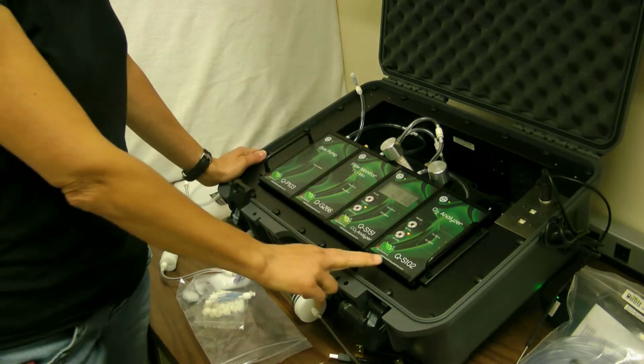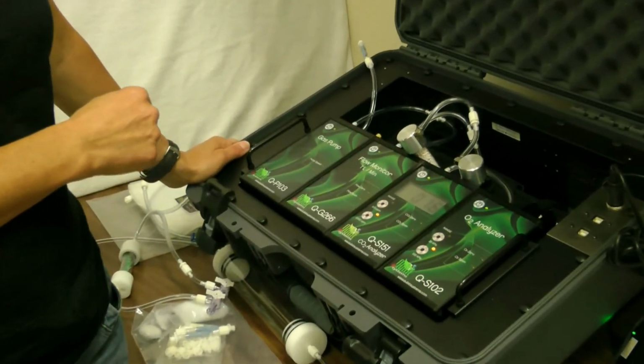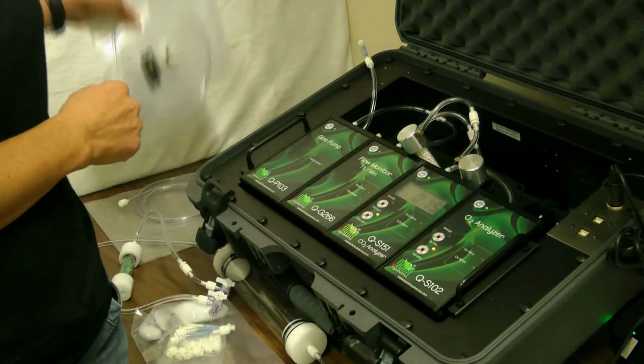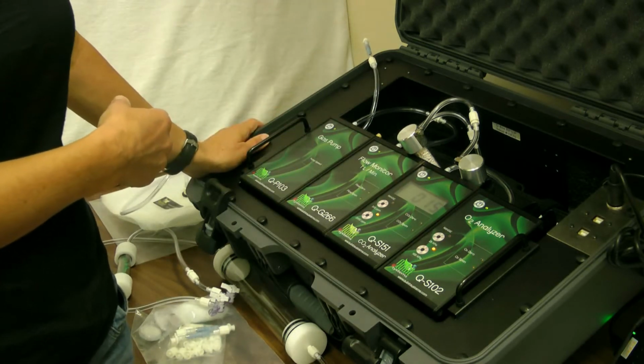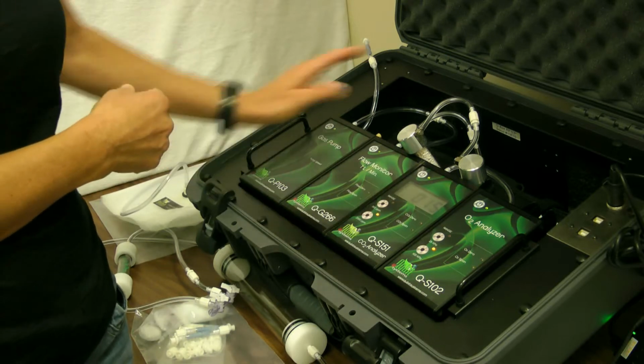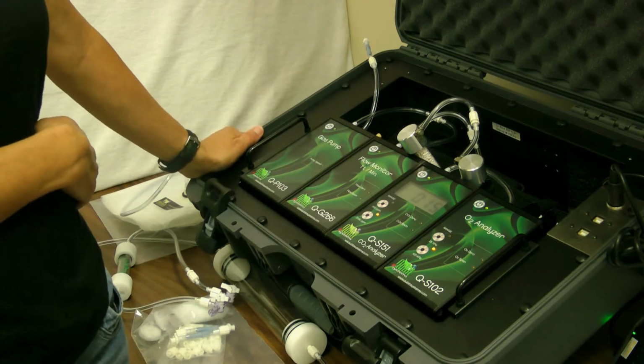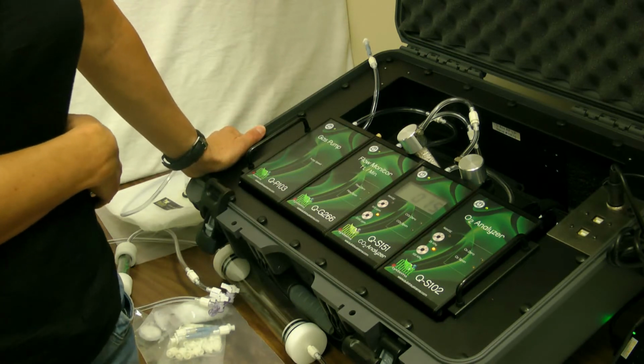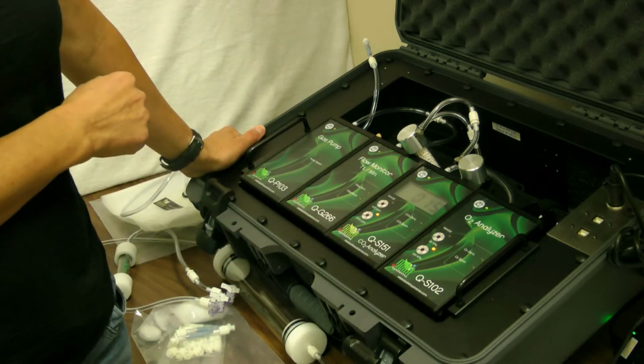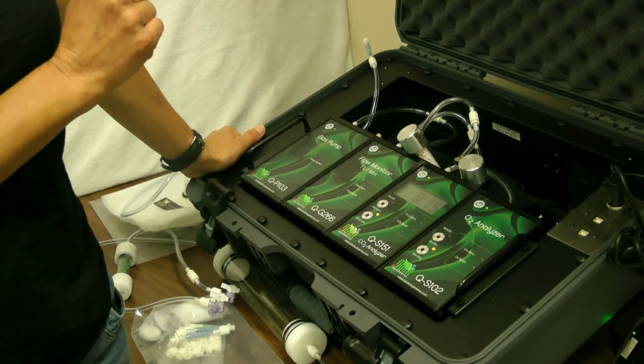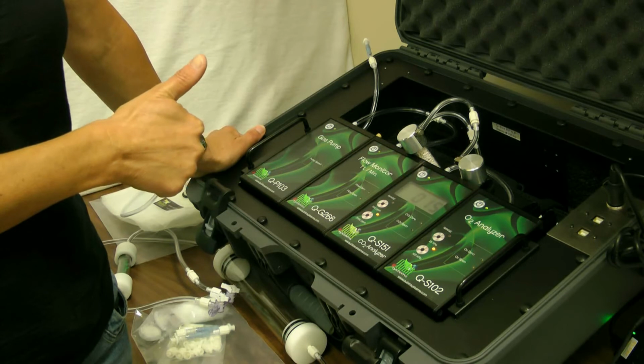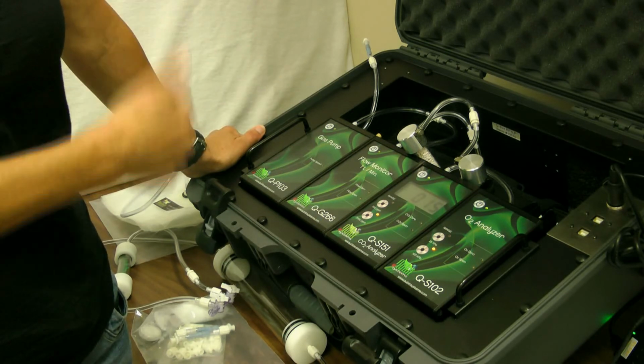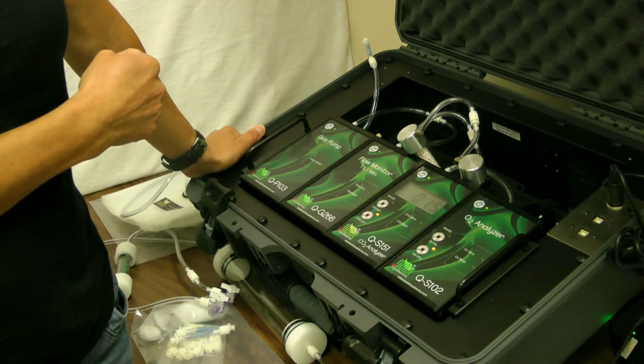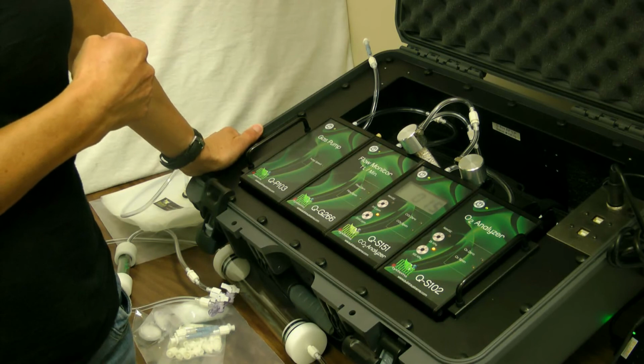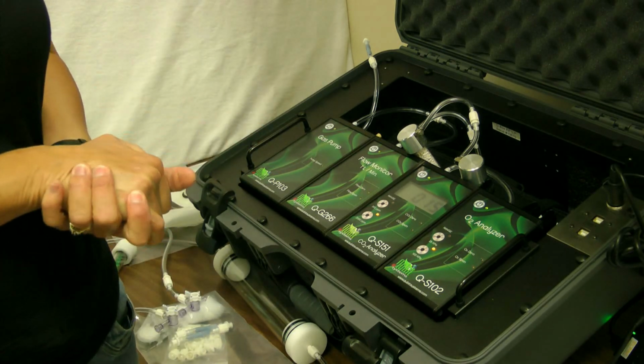For an oxygen analyzer calibration, we recommend that you use pure nitrogen to obtain your zero oxygen, and pure nitrogen can be filled inside this bag again and supplied to the system. And for the second point in calibration, you can use outside room air, which is dried through this drying column. And we know that the outside room contains 20.95% oxygen. So that second reading can be obtained by just using outside air. So you really only need 2 gas tanks for calibration of your sensors. One standard CO2 gas tank, like for 400 or 500 parts per million, and one pure nitrogen tank to get the zero oxygen reading. Okay, we are now ready to proceed to the second step, which is downloading your software.